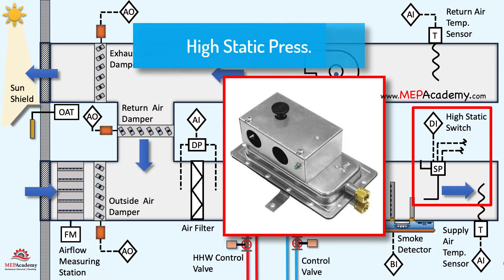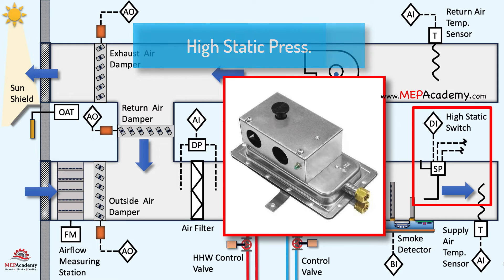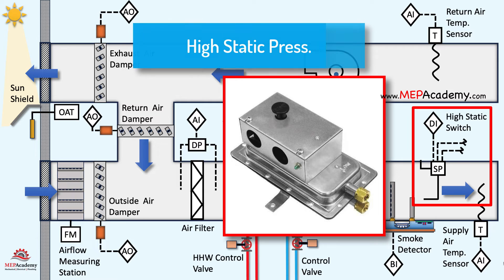High duct static pressure poses challenges in the event of a building fire when fire dampers are activated. During a fire, the closure of fire dampers results in downstream duct sensors detecting a pressure drop. Subsequently, these duct pressure sensors transmit signals to increase the air handler speed even further to restore normal operation. However, due to the closed fire dampers, the ramping up of the air handler causes an increase in duct pressure upstream of the fire dampers. This increase reaches a threshold where high static pressure switches intervene, cutting power to the variable frequency drive VFD and transmitting a signal to the DDC. Notably, switches in this specific application adhere to specifications requiring manual reset and dual outputs — one for disengaging power to the VFD and another for signaling the DDC.